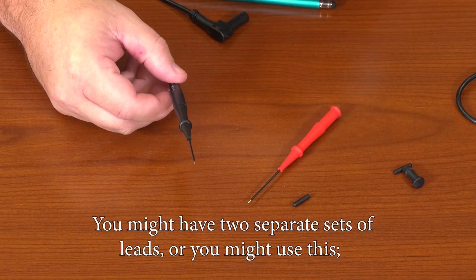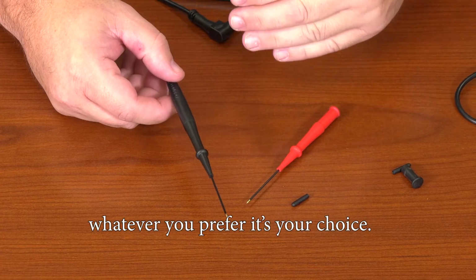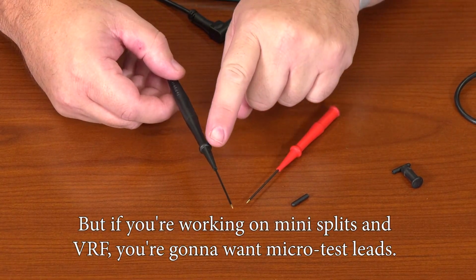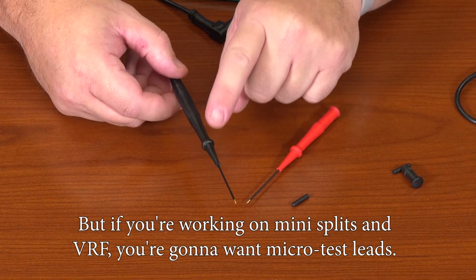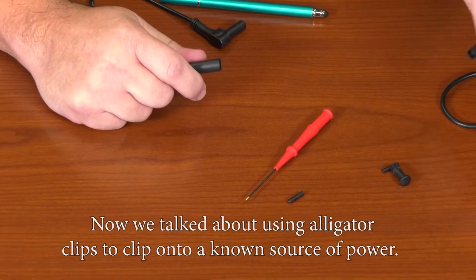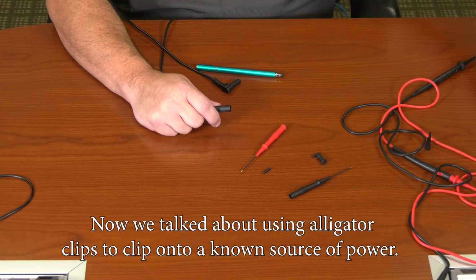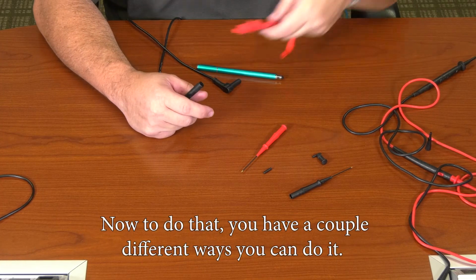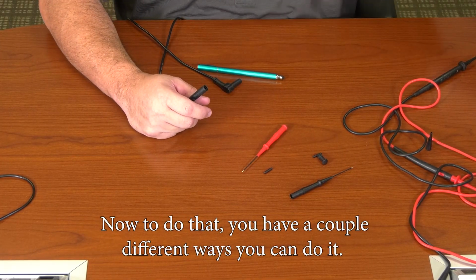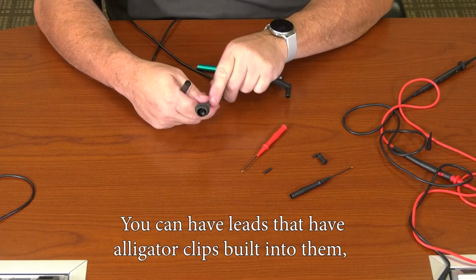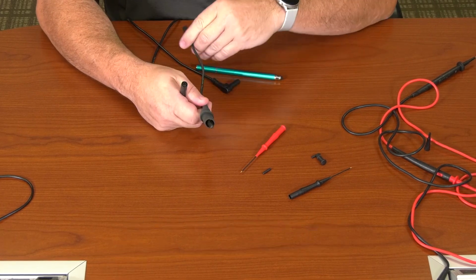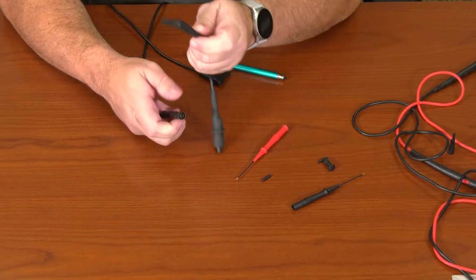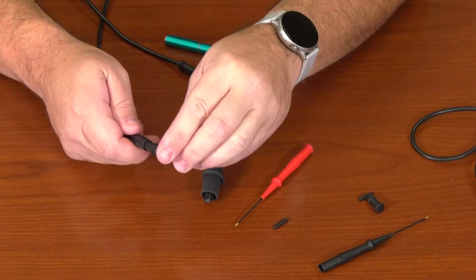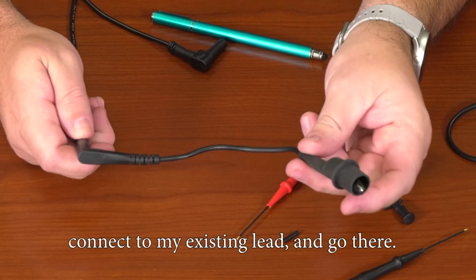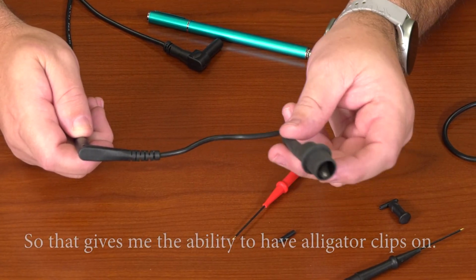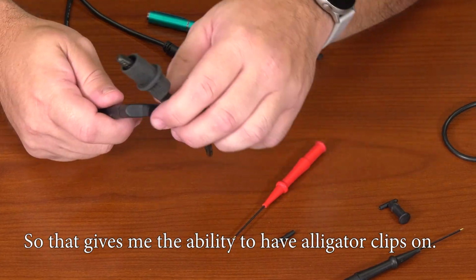You might have two separate sets of leads, or you might use this. Whatever you prefer, it's your choice. But if you're working on mini splits and VRF, you're going to want micro test leads. Now, we talked about using alligator clips to clip onto a known source of power. To do that, you have a couple different ways. You can have leads that have alligator clips built into them, or if I'm using this style of meter lead, again, I simply remove the plug, connect to my existing lead, and go there. So that gives me the ability to have alligator clips on.